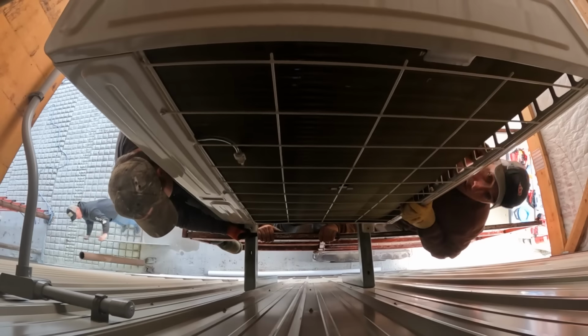So we actually custom fabricated some brackets out of some heavy duty 1/4 inch thick tube steel or similar to tube steel, and I would recommend doing the same thing. The nice thing about doing it this way is you can actually weld them up strong enough where you don't even need the angled piece that is going to be the additional support bracket for that L-shaped piece. And so I was able to make a really clean looking bracket that also didn't affect this entry point to the building. There's kind of an area where you could drive a skid loader through or something, so we wanted to get it up and out of the way as much as possible so that the unit wasn't going to get hit or hooked on or anything like that.